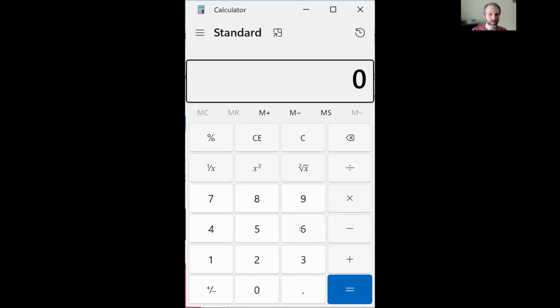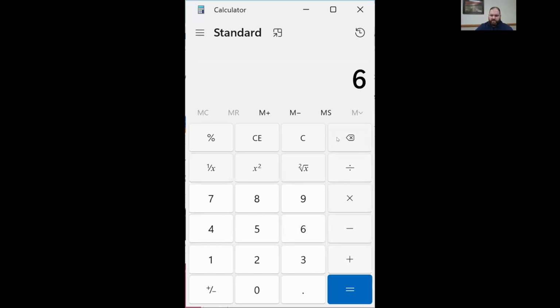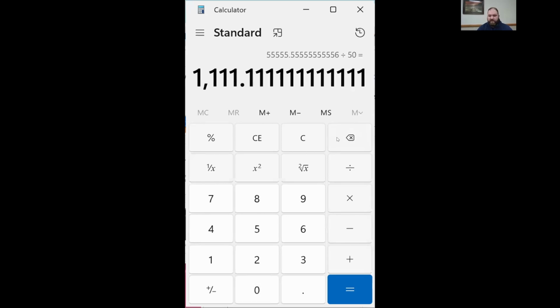Yep. So if I have a 60,000 BTU furnace, and I take that number and divide it by 1.08, which is my constant, and then divide that by my delta T, which is designed, we're just going to say it's 50 degrees. That's usually right in the middle. So if I was installing a furnace with a 60,000 BTU heating capacity, I would design my duct system for 1111 CFM. I've got a duct calculator on my phone.